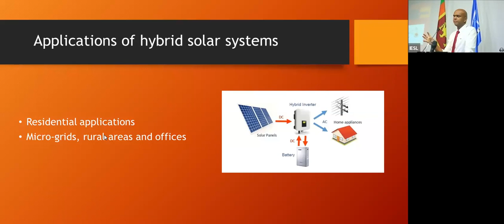So how to select a hybrid inverter? Similar to an off-grid inverter, we need to know the continuous power we are getting, maybe the continuous surge power or the instantaneous, since sometimes you need a high load to start pumps like that. The array size, the inverter charging capacity - most hybrid inverters have the capacity to charge the batteries through a diesel generator or through a set of solar arrays. So we need to know the maximum current it can handle, how fast it has to be charged, and the configuration, whether it's AC coupled or DC coupled, and the rest of it.